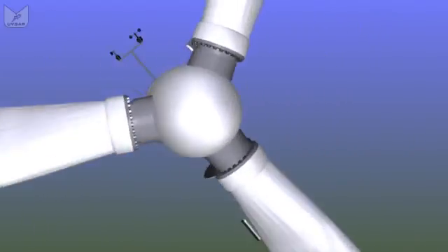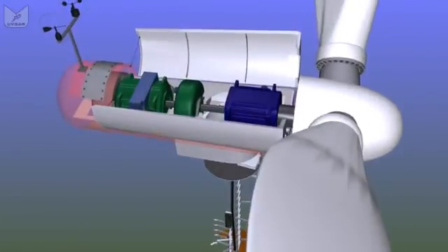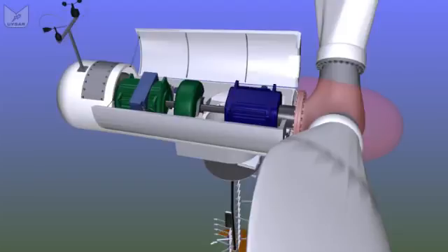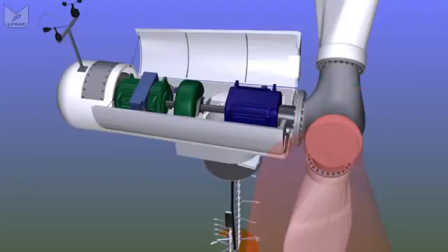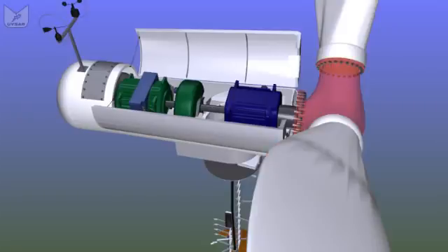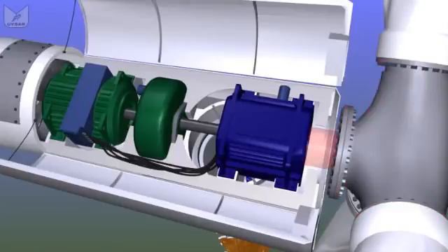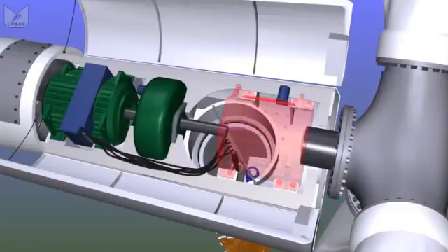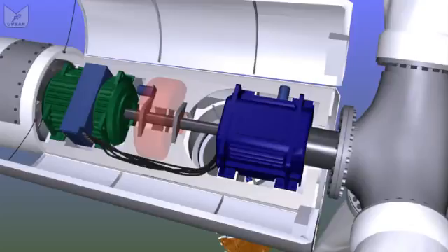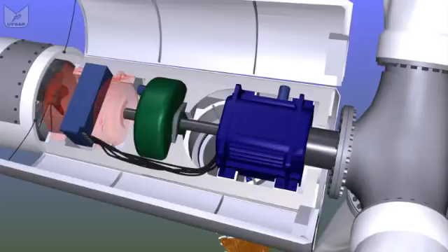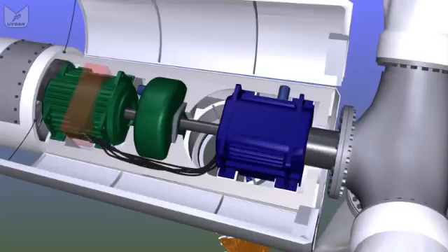At the front we have a similar fiberglass cowl protecting the hub, which is a steel casting on which we have bolted our 3 blades, and the blades can turn or pitch so that the angle they form with the wind can be varied. Out of the back of the hub we have a shaft which leads into the gearbox, then a high-speed shaft through a brake into a generator, and that generator then supplies the electrical power, as I say, at about 690 volts all the way back down the tower to the base.